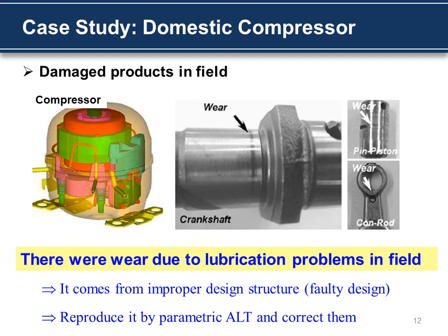This is a damaged compressor in the field. We found wear due to a lubrication problem in the field. It came from an improper design structure. To modify it, we should reproduce the faulty design by parametric ALT and correct it.